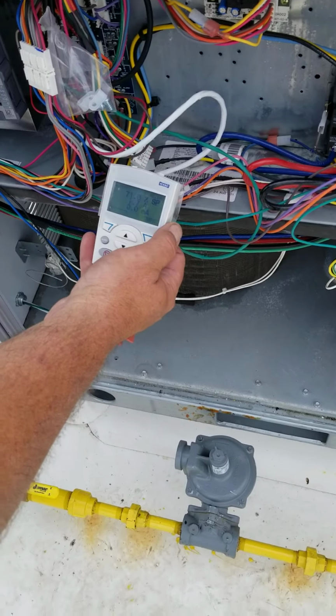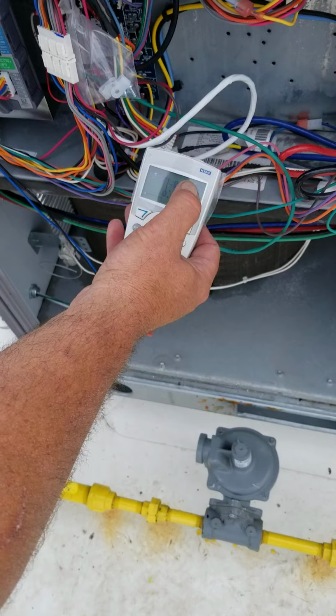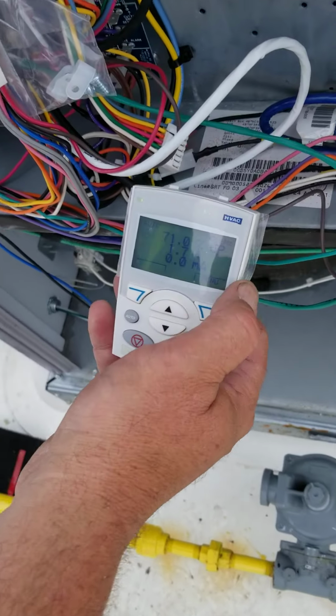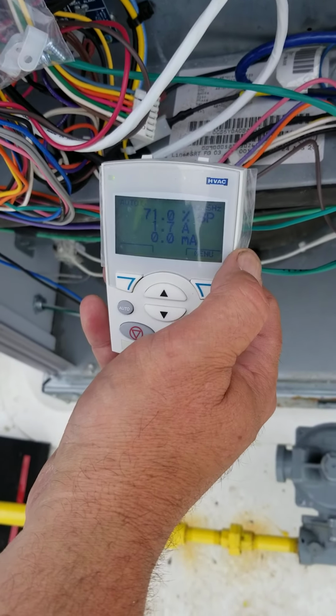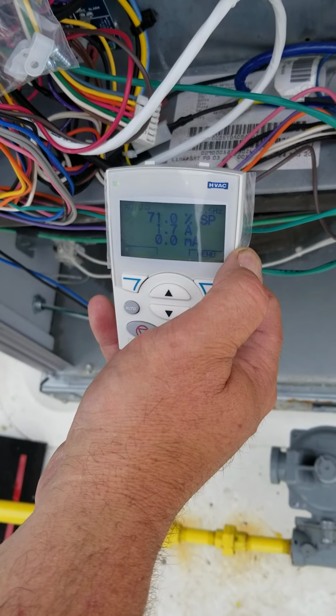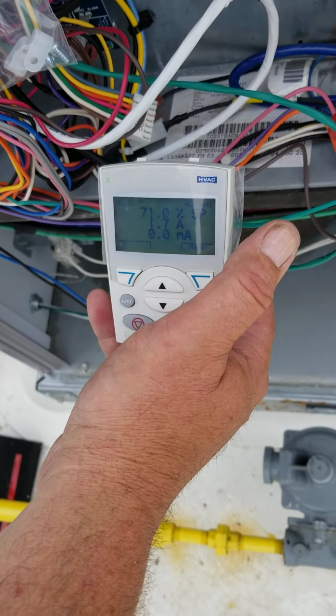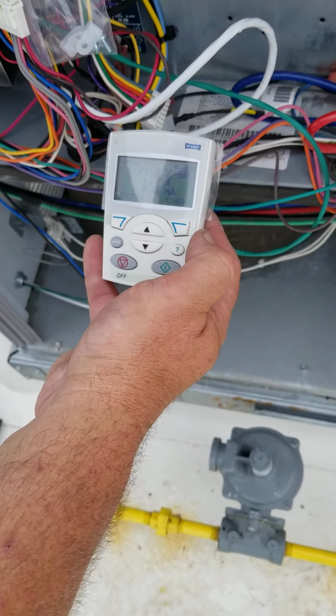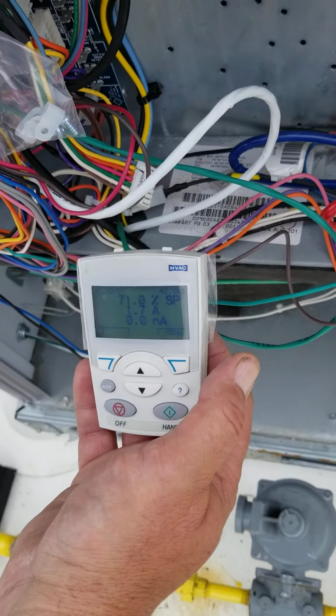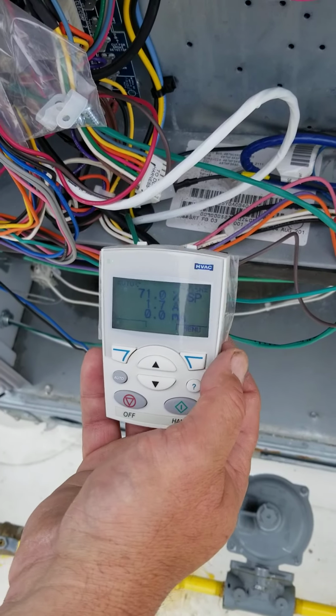So they give you the option of having this wire, so you can see right now we're running in auto. We're at 42 hertz, just a little over, which is 71% of full speed, drawing 1.7 amps. So if you ever had to do a reset here, maybe a goofy power thing happens and the blower's not running, come up and look at this.